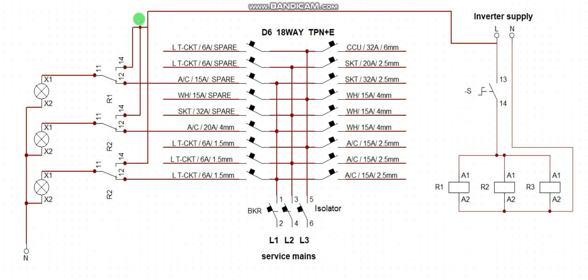This one is just for illustration. The three of them, one, two, three, will come parallel to your inverter supply while they enter the relay. All right. Then you feed the relay to the coil. Whenever you feed the inverter to the coil of the relay, whenever inverter comes active, these relays will be energized. Once they energize, the contact here will change from the original setting of the DB to your inverter supply. Then the load will remain the same.